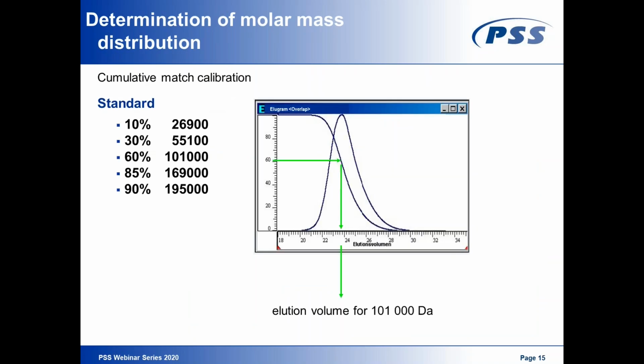How does it work with broad standards? I just want to show you here the cumulative match calibration that I already mentioned for the heparines. Because here you have just one standard, one broad standard, and you have a very detailed list of molecular weights for this standard. So as an example, you see here that, for example, at 10% eluted mass, you have a molecular weight of 26,900 Dalton. For 30, you have like 55,100, going up to 90% eluted mass, you have a molecular weight of 195,000.